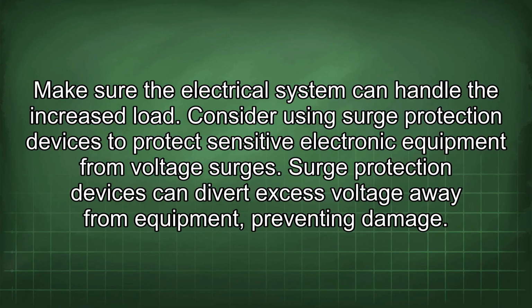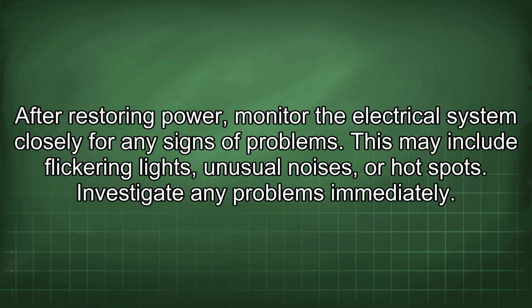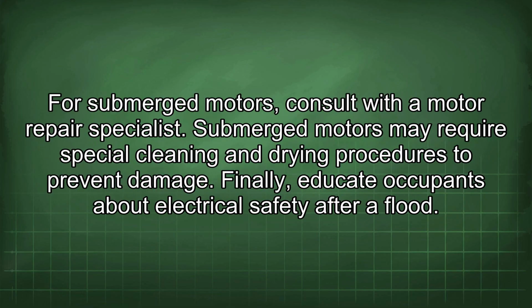Consider using surge protection devices to protect sensitive electronic equipment from voltage surges. Surge protection devices can divert excess voltage away from equipment, preventing damage. After restoring power, monitor the electrical system closely for any signs of problems. This may include flickering lights, unusual noises, or hot spots. Investigate any problems immediately. For submerged motors, consult with a motor repair specialist. Submerged motors may require special cleaning and drying procedures to prevent damage.